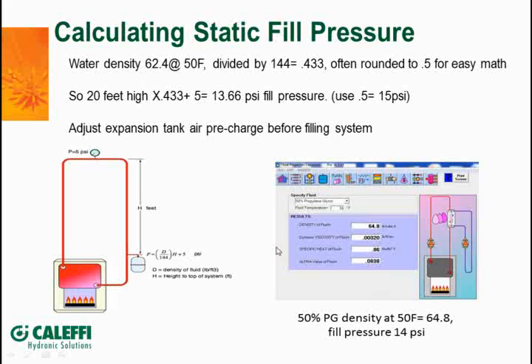Now, again, going back to the hydronic design software program that I showed you earlier, they've actually got a fluid table module in here. So if you are going to use a different type of fluid, in this example I put in a 50% propylene glycol. We're going to fill that at a 50-degree fluid temperature. You can put the temperature, and you can choose different types of glycol: ethylene glycol, propylene glycol, different percentages of mix. You can see it changes a little bit from water. We've got 64.8 here, where the density of water at 50 degrees is 62. So it doesn't make a huge difference in this example. It went from 13.66 to 14 psi, but that table is available for you to use so you can get that dial right into the exact number.